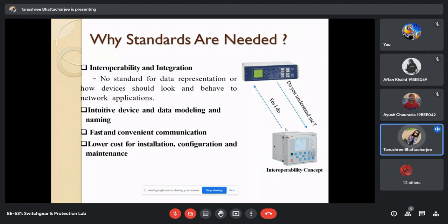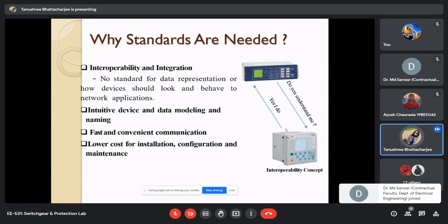We need these standards because, as I've told you, there are many manufacturers of these intelligent electronic devices. If a substation uses devices from different manufacturers, we need to make them communicate, since configurations differ depending on the device or manufacturer. So they publish a standard used worldwide so that one IED can communicate with another and operations can run smoothly.